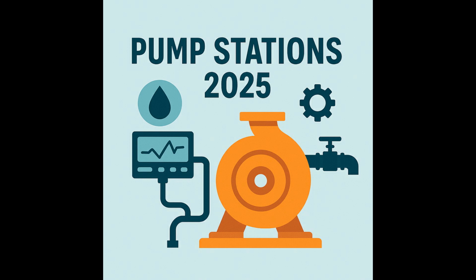But what's the actual danger if we stray too far or too often? What critical concepts are at play here that make staying in the POR so vital? That's where we get into something called net positive suction head, or NPSH, and a very destructive phenomenon called cavitation. Okay, NPSH? NPSH is basically a measure of how much pressure is available at the pump suction compared to the minimum pressure needed to avoid this cavitation problem. There are two parts. NPSH available, NPSHA, which is the pressure the system provides, and NPSH required, NPSHR, which is what the pump needs, and that comes from the manufacturer. Right. The critical part is maintaining a healthy margin, that's simply NPSHA minus NPSHR, to ensure reliable operation. You need that buffer.